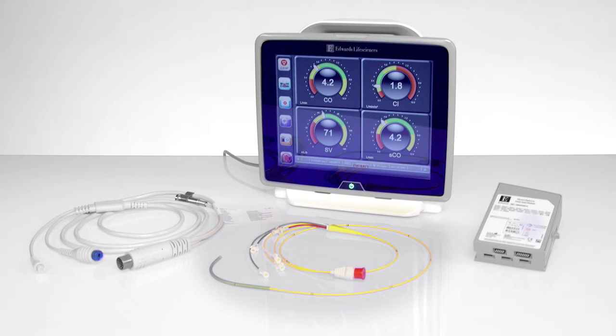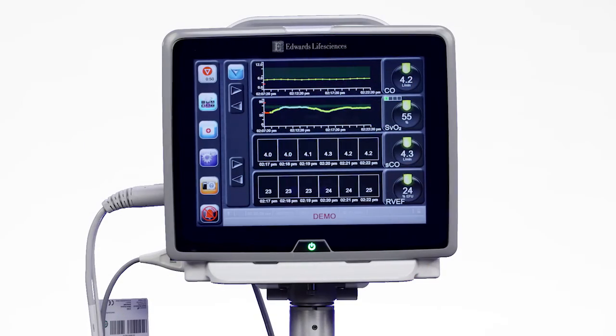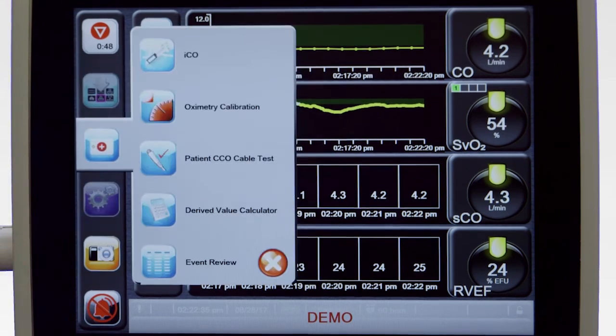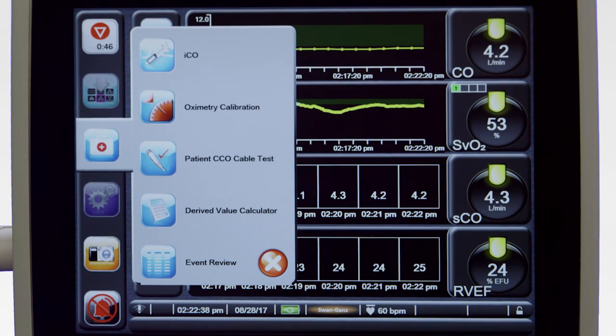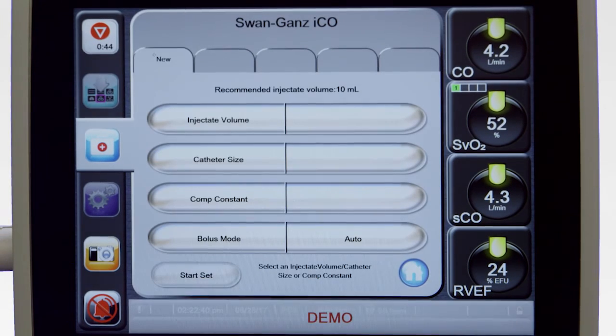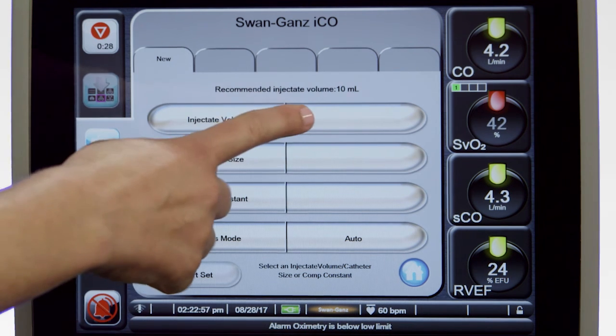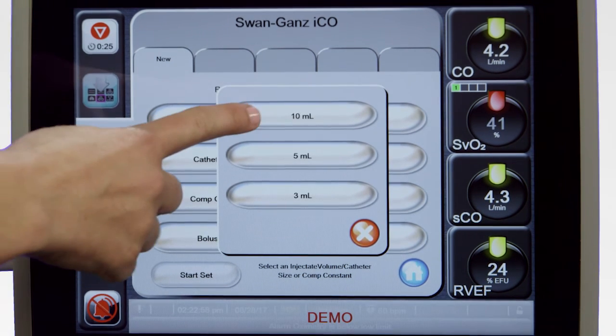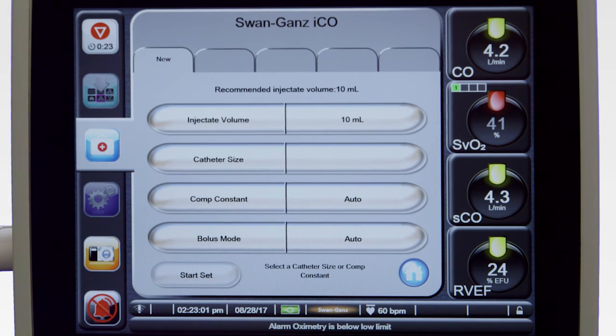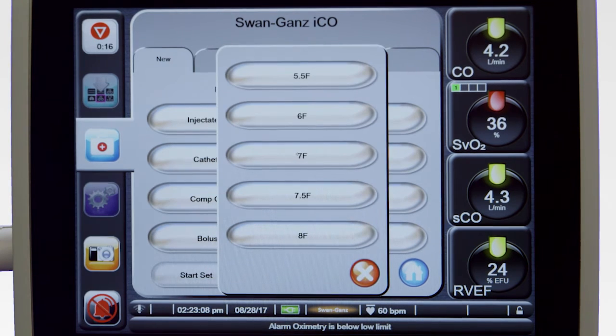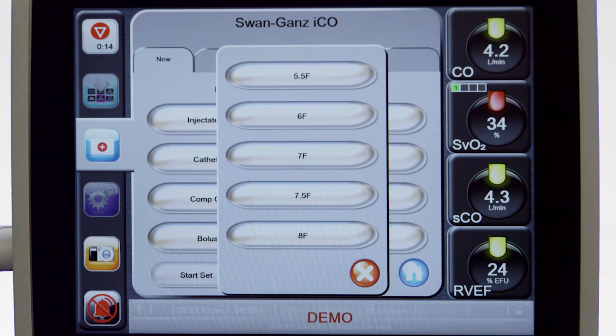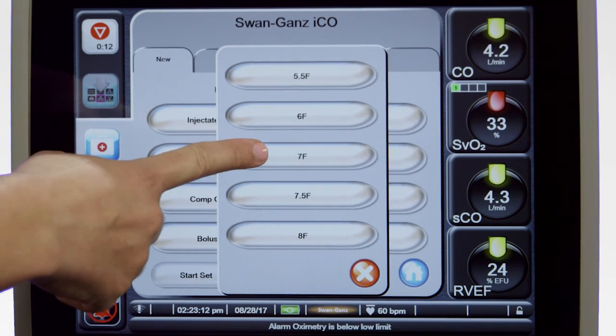To configure the HemoSphere Advanced Monitor for ICO monitoring, touch the Clinical Actions icon in the menu bar. Then select ICO. Specify the desired injectate volume from the list of values provided. Once a value is selected, the computation constant is automatically set. Select a catheter size from the available list. Choosing a value here also sets the computation constant.